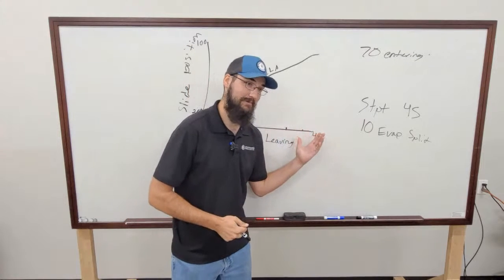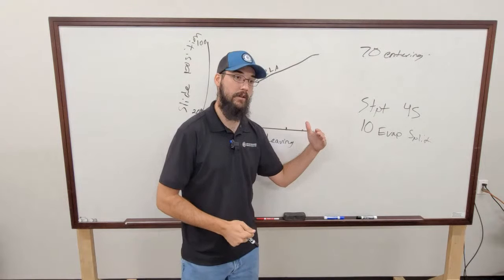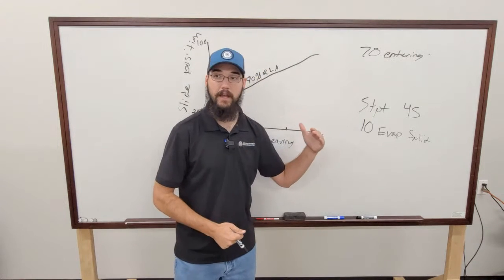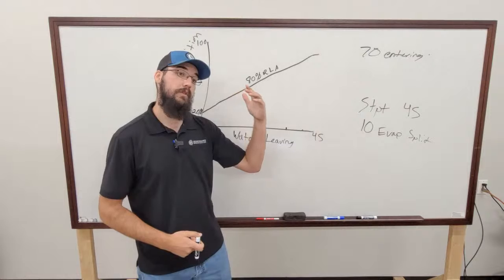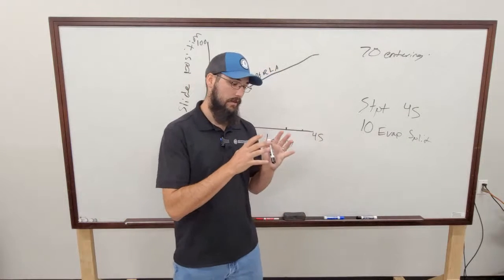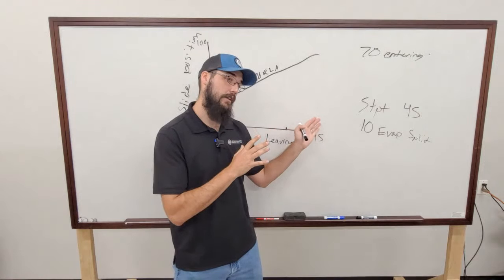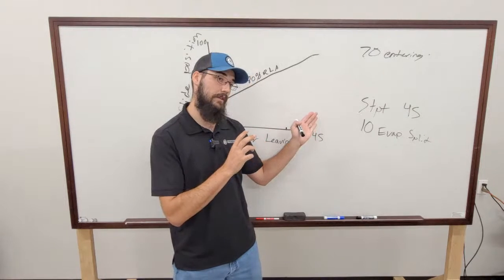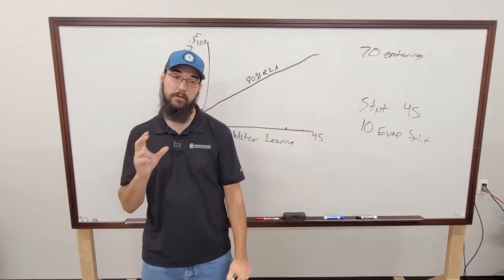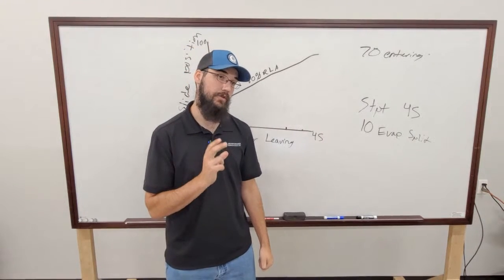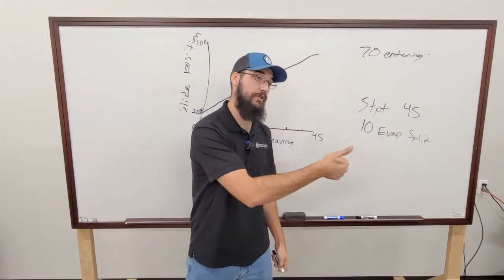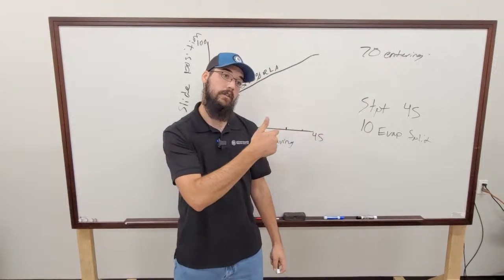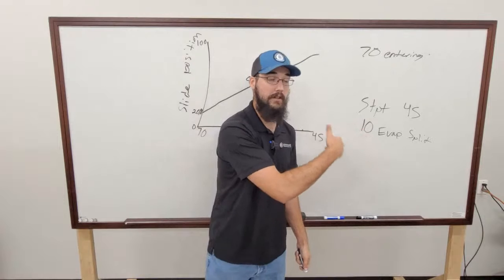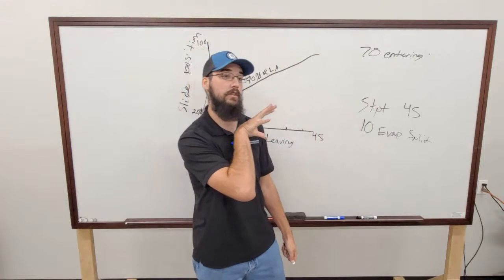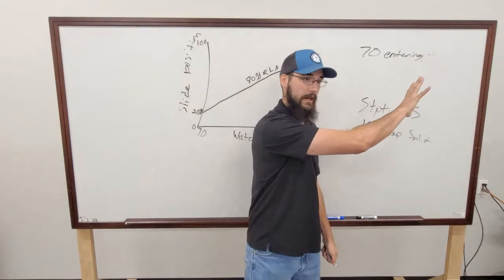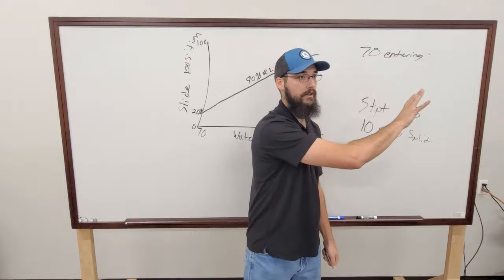So this is current limiting. Once we hit that pull down, we're going to limit that so that it can't overstage itself. Because when you have really high load conditions, the load and pull down are very unstable conditions. And what you don't want to do is push your head pressure too high. You don't want to add more stress and waste energy, because if you allow that system to completely stage at maximum at pull down, you're burning a lot of electricity at that time.